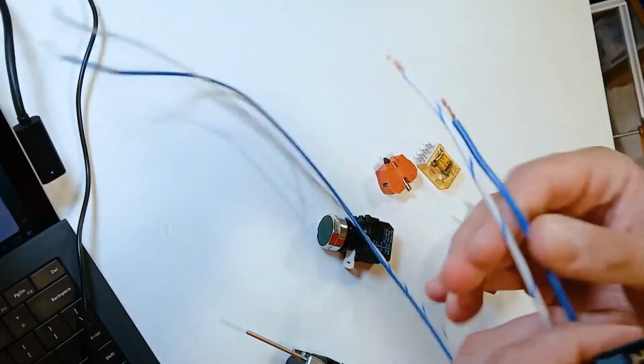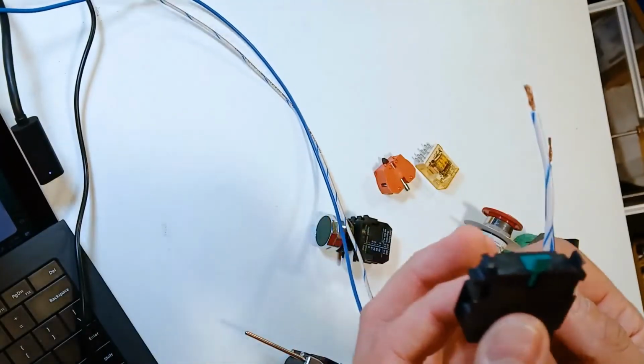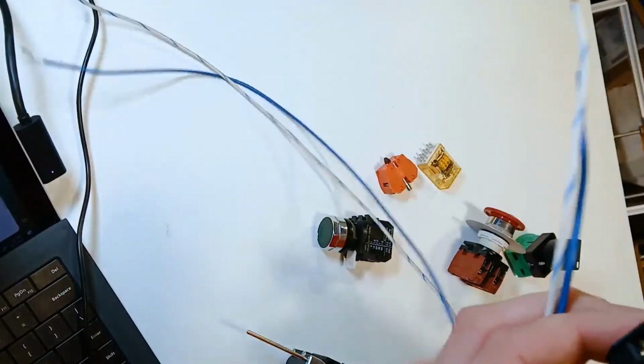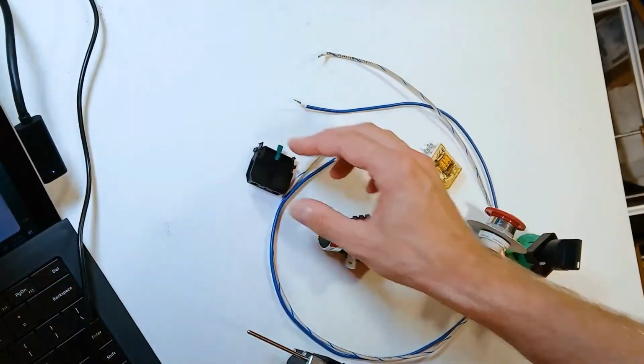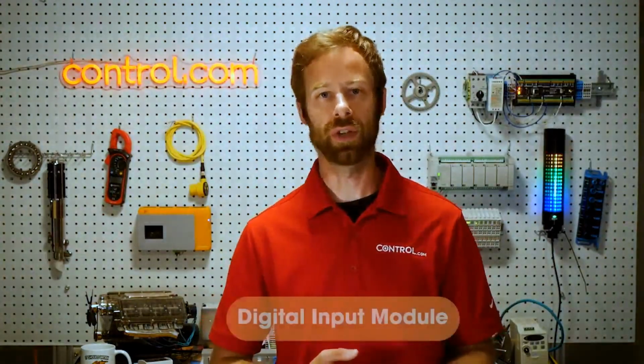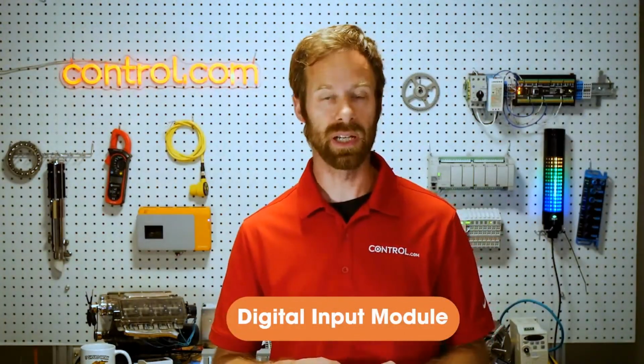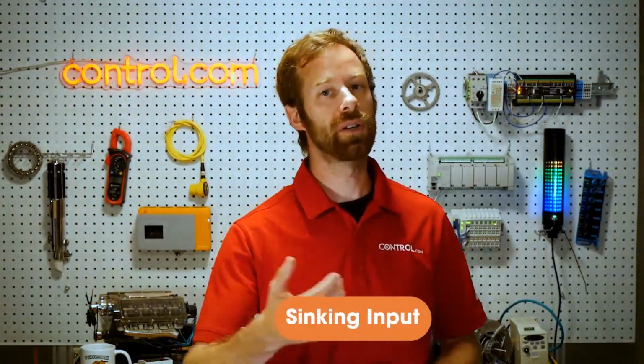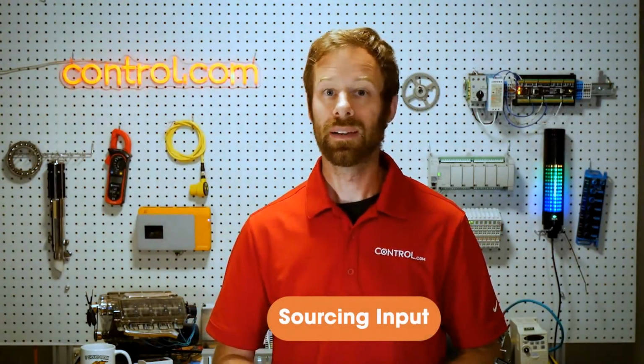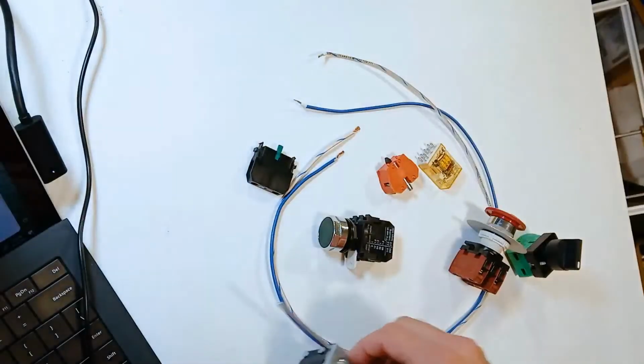So what do we need to connect it? Well, really all we need is just two wires, one for electricity to flow into this physical contact, and another one for it to flow out. When we connect it to the control system, what we're going to look for is a digital input module. That digital input is going to either allow current to flow in, which is what's called a sinking input, or it sends current out, which is what we call a sourcing input. The great thing about these electromechanical switches is that they don't care which direction electricity is going, either coming from the module or going to the module. As long as we connect our power supply properly, there's no such thing as a polarized mechanical switch. And therefore, we can hook them up either direction we need to fit the constraints of the control system.